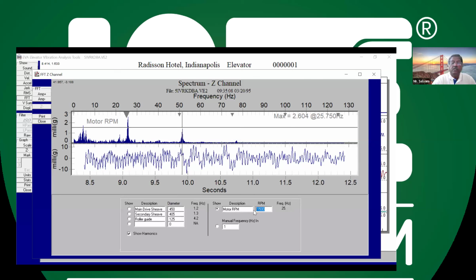If you put 1350 RPM, you will get the corresponding rotating frequency, 22.5. In this particular case, for example, a 1500 RPM motor, I think it is around 25 hertz. It's closer to the motor related issue. But this is only one snapshot.